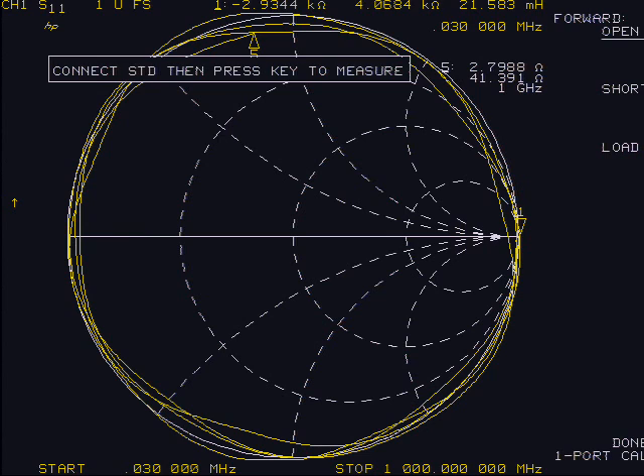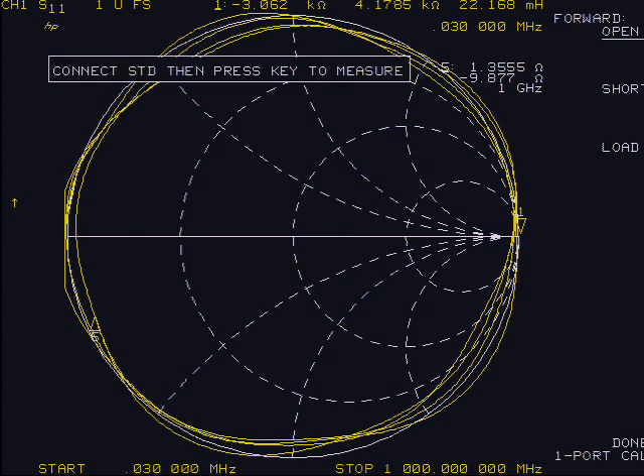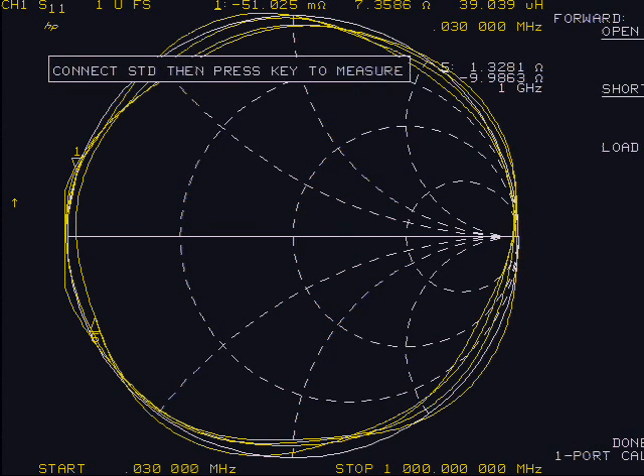After the correct calibration component is connected to the port 1 cable end, press the soft key associated with the cal component: open, short, or load. You will hear a beep when all the measurement points are completed. After the final cal component beeps, push the lower right done one-port cal soft key.